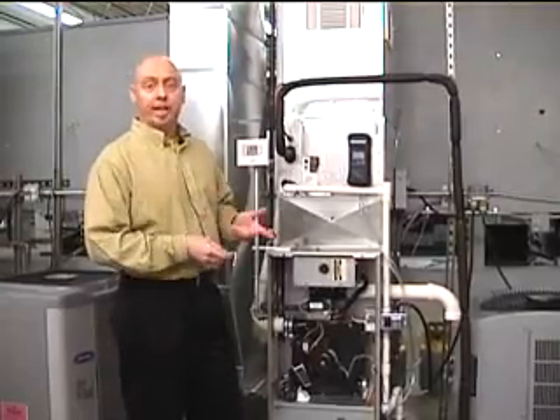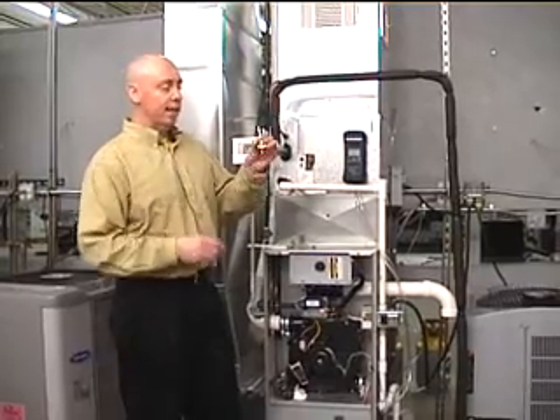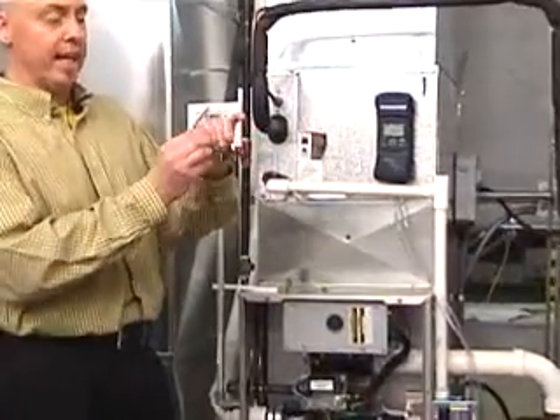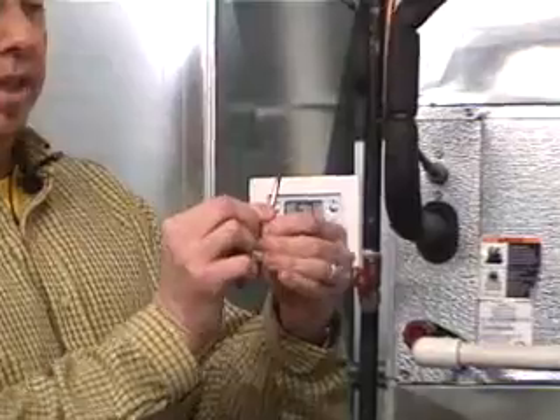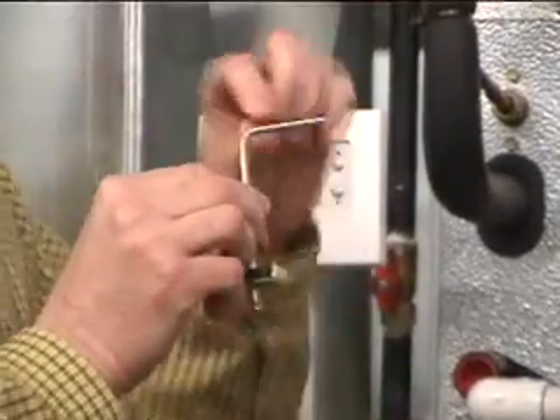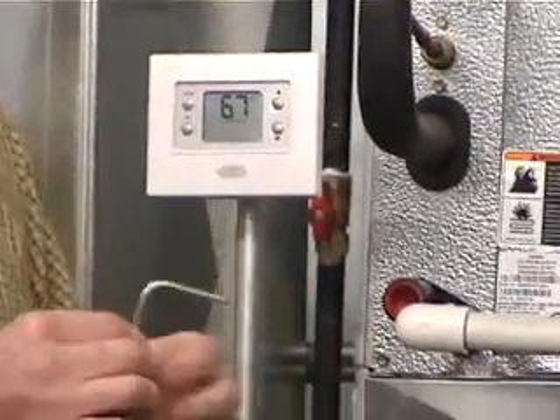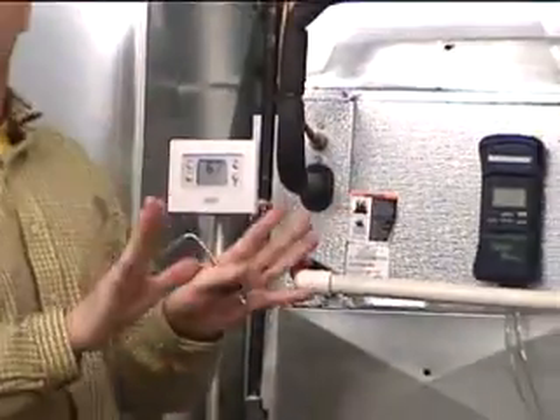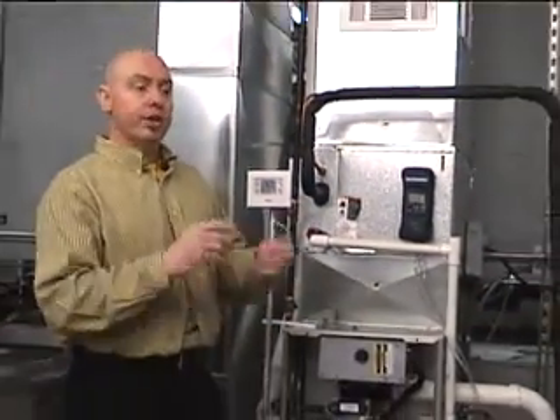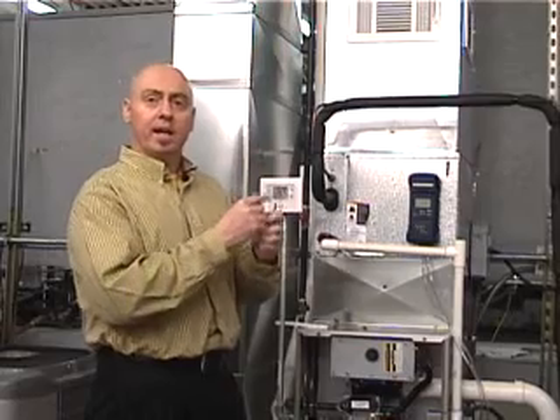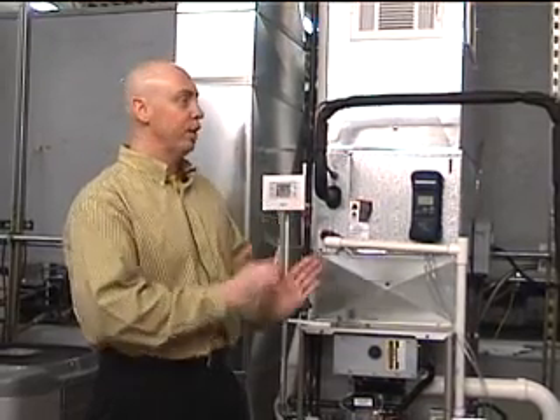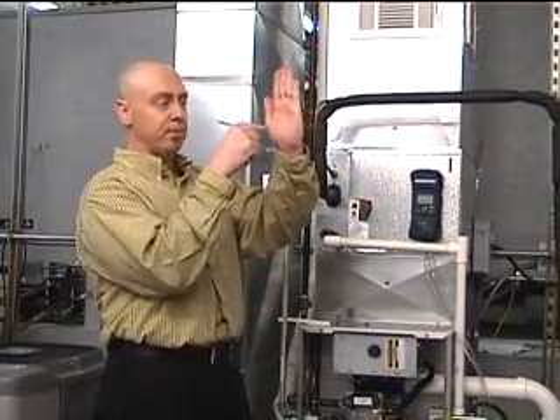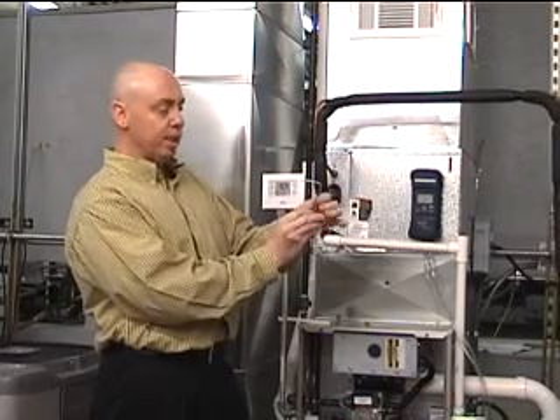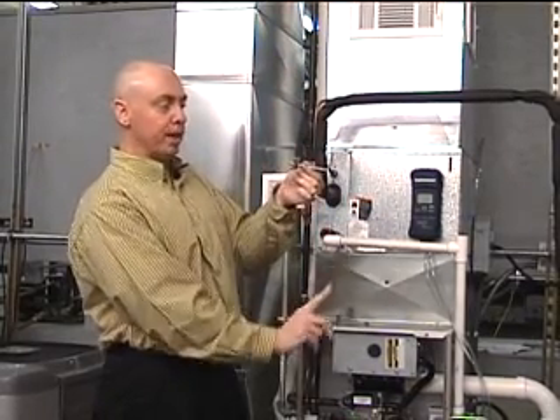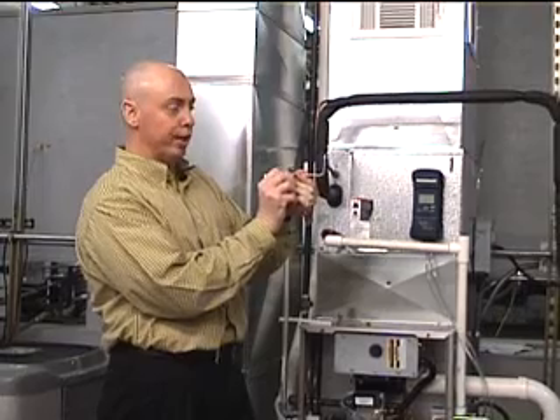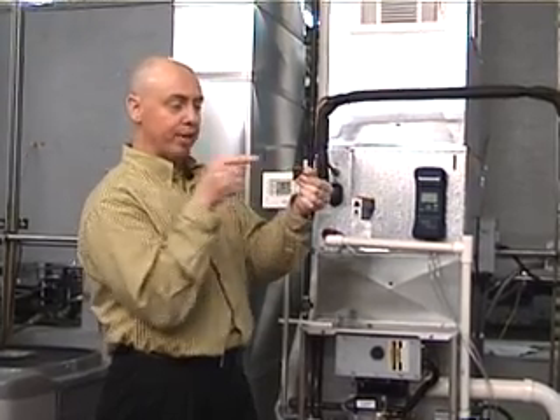When accessing the reading, I recommend you use something like this. This is what we refer to as a static probe. If you look at it, it is bent at 90 degrees. It is actually welded shut on the end, and it has holes on the side. When you are checking static pressure, since it is the pressure that is exerted on all the walls of the duct all the way around, your sensing probe inlet has to be 90 degrees to the airflow. So if the airflow is going this way, your inlet sensing probe is this way. When you put this into the ductwork and your supply air is going this way, you point it in the direction of the airflow, and you'll see that the sensing probes are 90 degrees to the airflow.